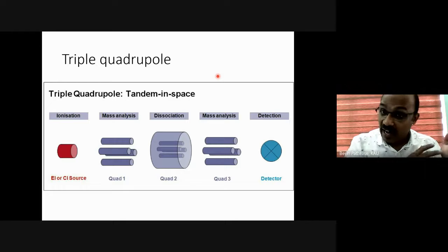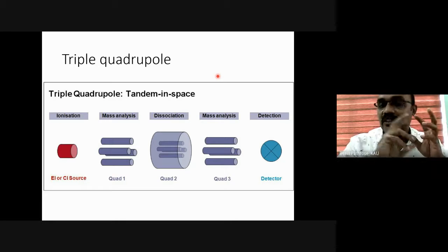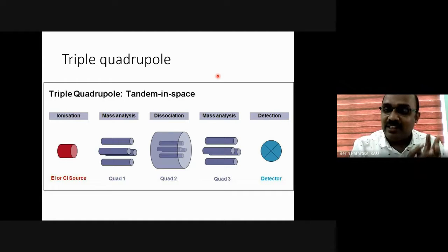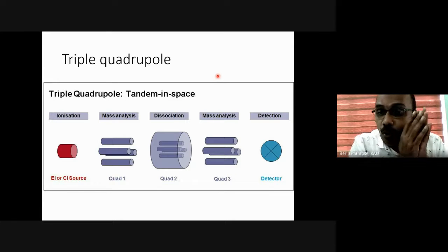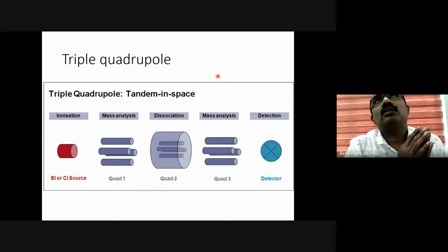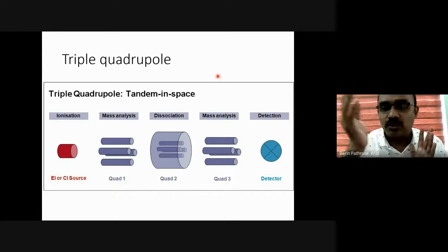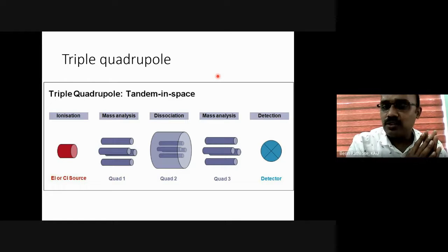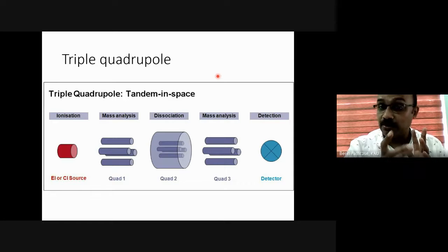it changes the voltage, and it switches the voltage from plus to minus, minus to plus, plus to minus, minus to plus. Also it varies its voltage from, I think, 1000 to 10,000 or something. I forgot the exact range. Different instruments have different ranges. So within a short period of time, it switches the voltage plus or minus and charges the quadrupole.